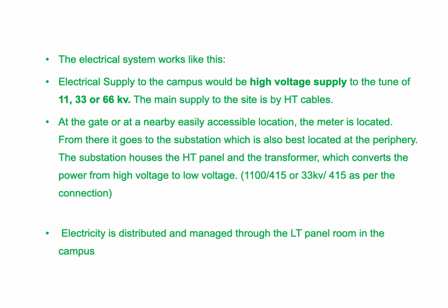At the gate or at a nearby easily accessible location, the meter is located. From there, it goes to the substation, which is also best located at the periphery. The substation houses the HT panel and the transformer, which converts the power from high voltage to low voltage that can be used, for example, 11000 by 415 or 33000 by 415 as per the connection. Electricity is distributed and managed through the LT panel room in the campus.